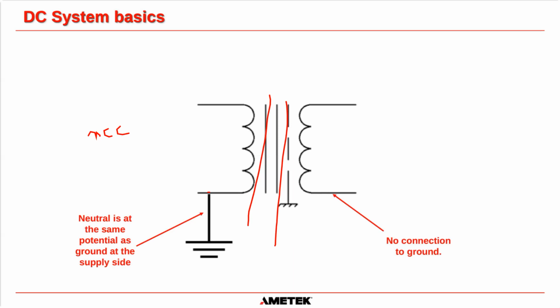The primary windings here do not physically touch the secondary windings here. The power is transferred using electromagnetic force and induction. The core of the transformer is magnetics. If you have a current flowing through the primary, that will induce a current flowing through the secondary, but there is actually no electrical connection between the two. So as you can see on the right-hand side, on the secondary side here, there is no connection to ground whatsoever on this very simple drawing. Okay, so we have a connection to ground on the primary, but we have no connection to ground on the secondary.